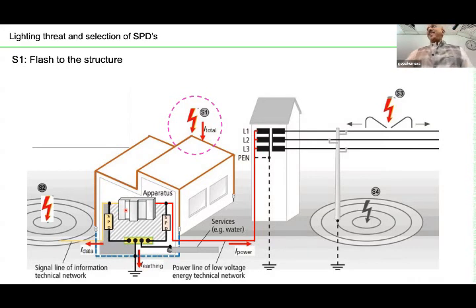So in modern buildings, the best way is to use the steel of the structure as the down conductor, because in our construction we use steel. There are columns, there are slabs. Make use of that steel and ensure that the entire building is able to handle the lightning current. So, which is the best way?